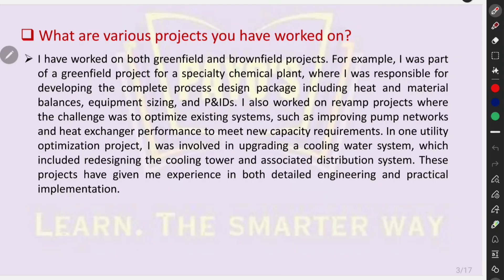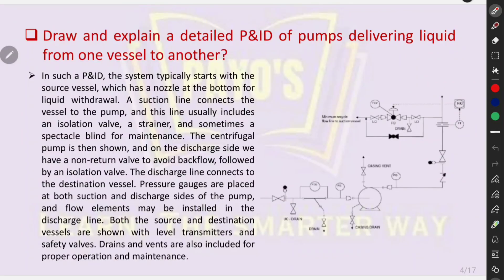These projects have given me experience in both detail engineering and practical implementation. Could you explain a detailed P&ID of pumps delivering liquid from one vessel to another? In such a P&ID, the system typically starts with the source vessel, which has a nozzle at the bottom for liquid withdrawal. A suction line connects the vessel to the pump, and this line usually includes an isolation valve, a strainer, and sometimes a spectacle blind for maintenance. The centrifugal pump is then shown, and on the discharge side, we have a non-return valve to avoid backflow, followed by an isolation valve. The discharge line connects to the destination vessel. Pressure gauges are placed at both suction and discharge sides of the pump, and flow elements may be installed in the discharge line. Both the source and destination vessels are shown with level transmitters and safety valves. Drains and vents are also included for proper operation and maintenance.